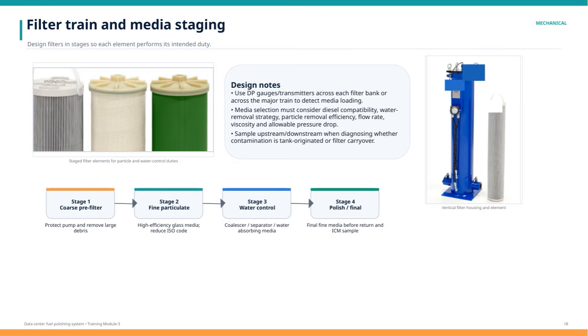Moving to Stage 2, we incorporate a fine particulate filter made from high-efficiency glass media. This stage significantly lowers the ISO cleanliness code, removing smaller particles to maintain fuel quality. Stage 3 focuses on water control, employing a combination of coalescers, separators, and water-absorbing media. Managing water content is critical as it helps prevent corrosion and microbial growth that could harm equipment. Finally, Stage 4 is the polishing or final filtration stage. It uses fine media to ensure the fuel is as clean as possible before it returns to the system or undergoes SCM sampling.